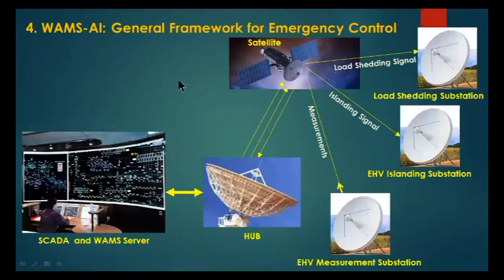This slide shows a typical framework for emergency control. There is the WAMS server and, for example, a measurement substation. Measurements are collected and taken through the satellite and hub to the WAMS server. The WAMS server, along with the supervisory control and data acquisition system, performs state estimation and filters out noise. Finally, it communicates the control action through the hub and satellite to various substations. For example, an islanding signal can be given to an extra high voltage substation, and similarly, a load shedding signal can be given to specified substations. This is the general framework for emergency control in case of stability or security issues.